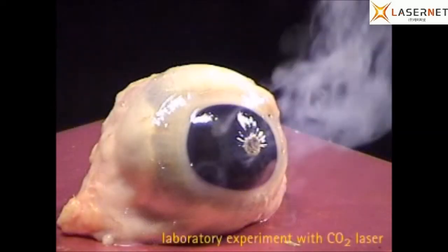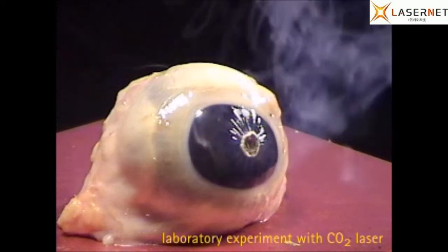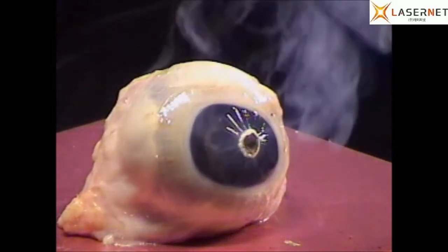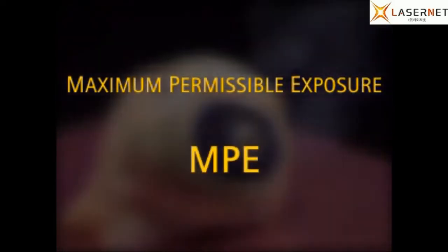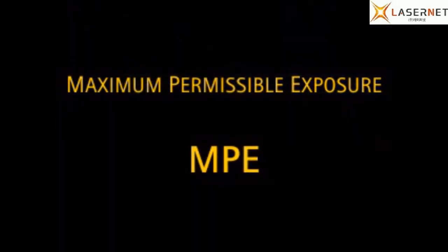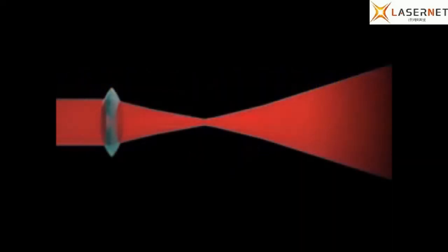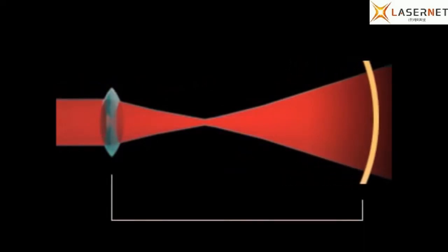Tissue is only damaged if the irradiance exceeds a certain threshold. This threshold is also called the maximum permissible exposure, or MPE. The MPE depends on the wavelength and the exposure duration. MPEs for the eye and skin are the same in some parts of the spectrum, but different in others. The MPE may be exceeded within a certain region from the laser aperture. This region is called the nominal hazard zone.